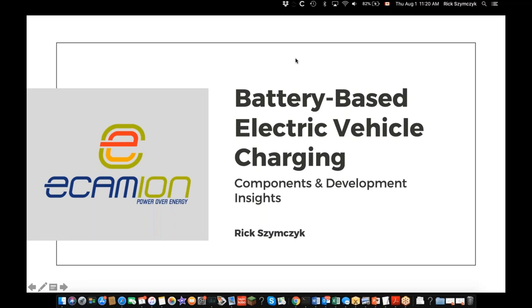What we have adapted over the last year and a half to two years is a technology that leverages energy storage to provide a fast charging service to electric vehicle customers. Our contribution is to provide electric vehicle customers a fast charging experience where the utility's or the facility's ability to deliver is constrained, either through infrastructure or cost. Customers are demanding tens — and we expect soon hundreds — of kilowatts of power where the facility is unable to provide that. One of the very public use cases is across the Trans-Canada Highway, where we are developing 150 kilowatts of power distributed across three dispensers to provide that service, which would ordinarily not be possible.